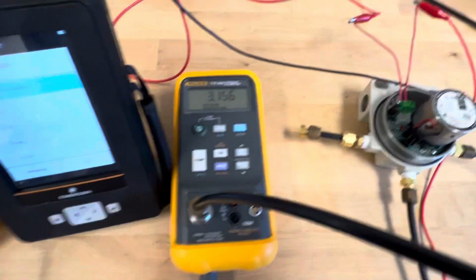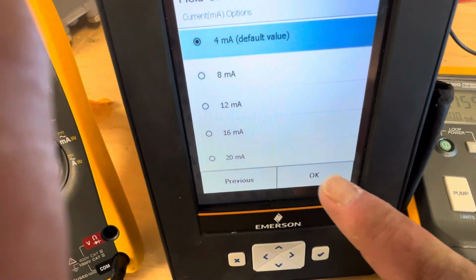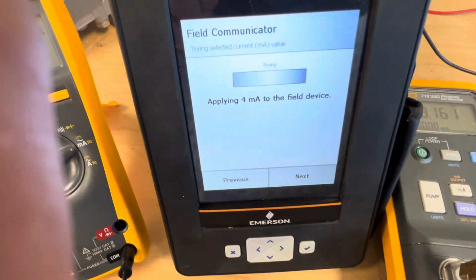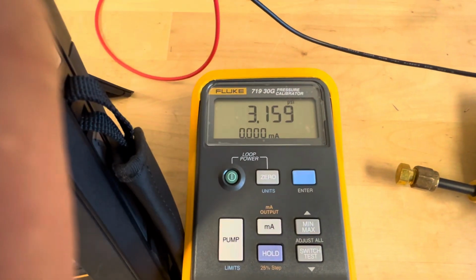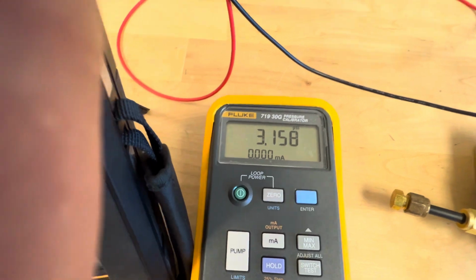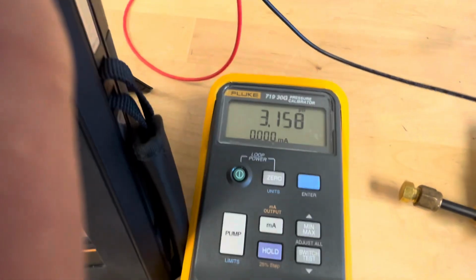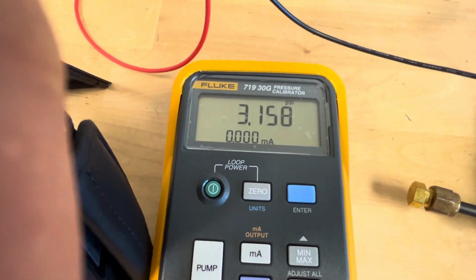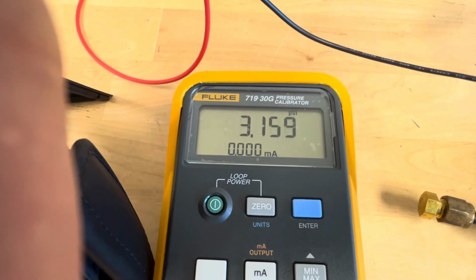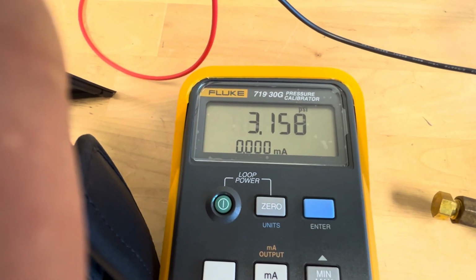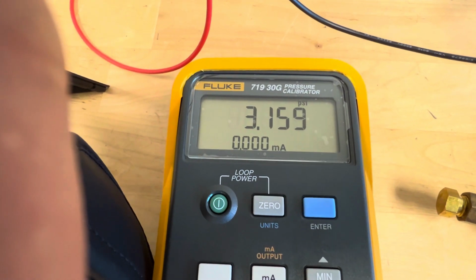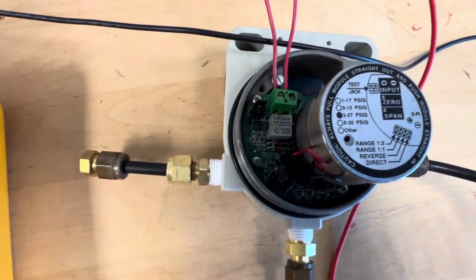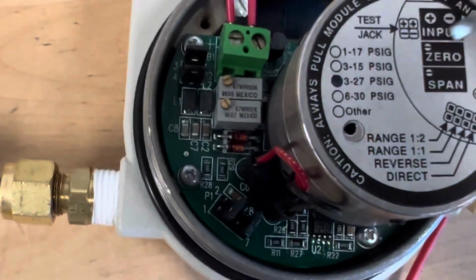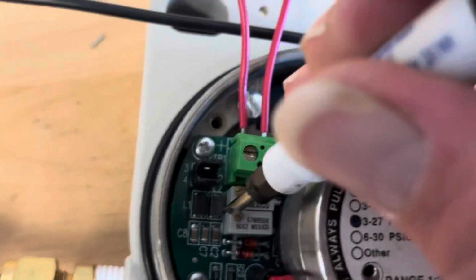All right, so looking at our zero right now, we see that when we supply 4 milliamps, we hit OK, that we're at about 3.159 PSI. And that's not too bad, but I want to go to at least an accuracy of the tenths place. So 3.0, and I'm not going to worry about the 2 numbers after that. So what I'm going to do here, I get my screwdriver into the slot on this potentiometer.